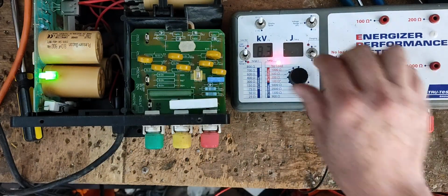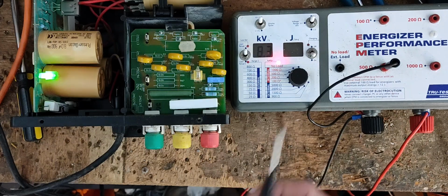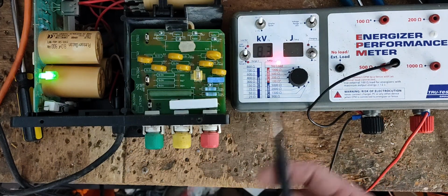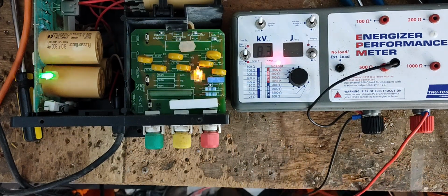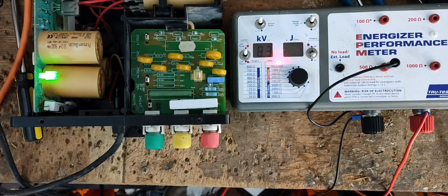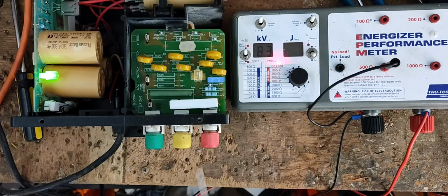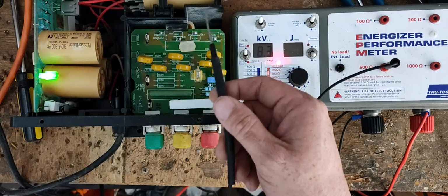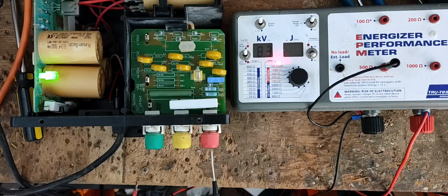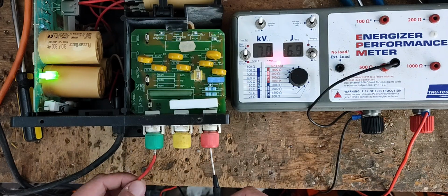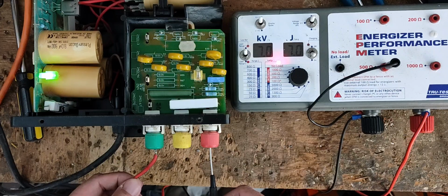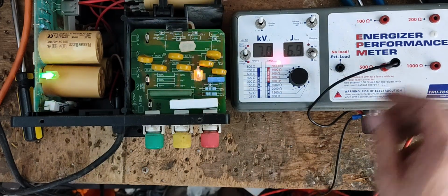We'll put a 500 ohm load on there. Now, what the joule output is supposed to be - this is a 15 stored joule unit, so probably 10, 8 to 10 output joules at max load is somewhere in that range. With the capacitor being a little lower, it may not get that high. We're already at about 7 joules, 7,000 volts with a 500 ohm load.